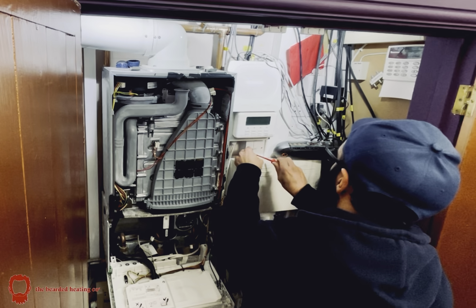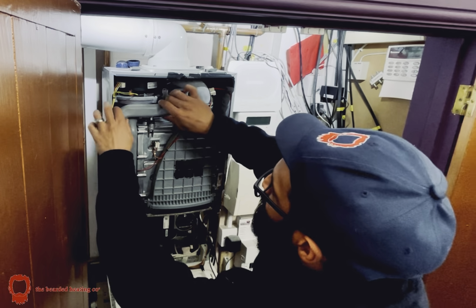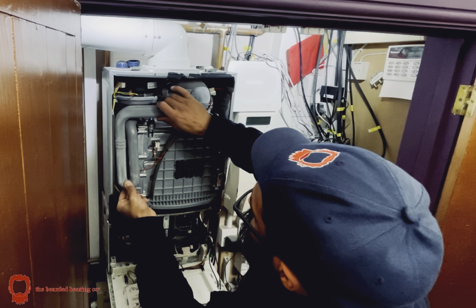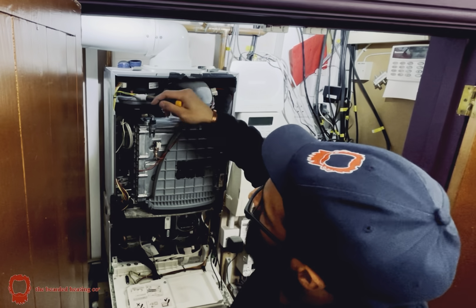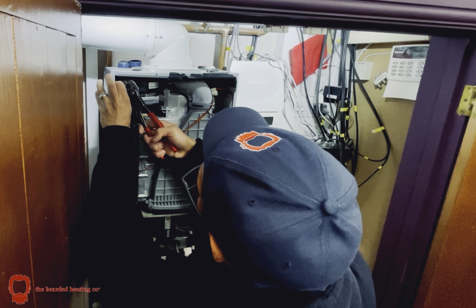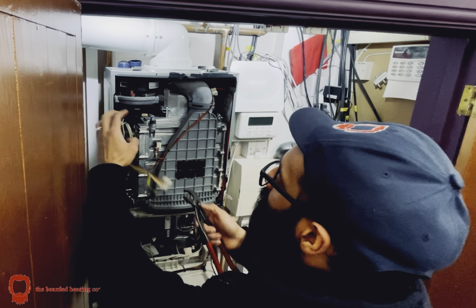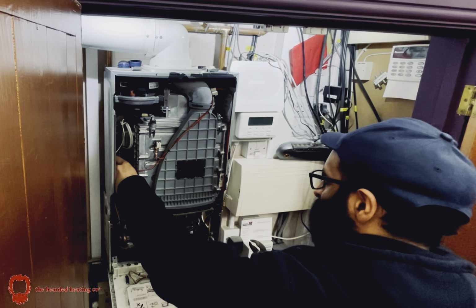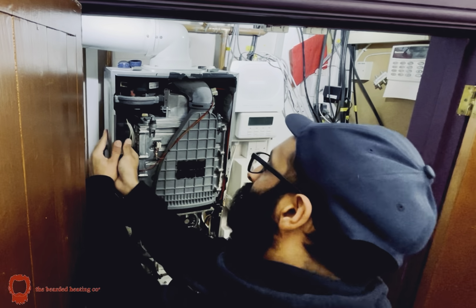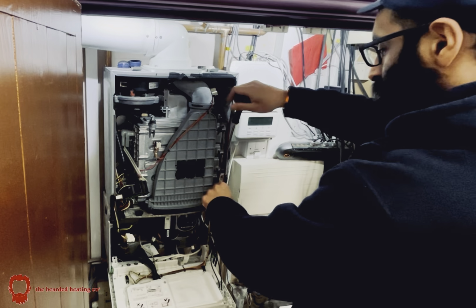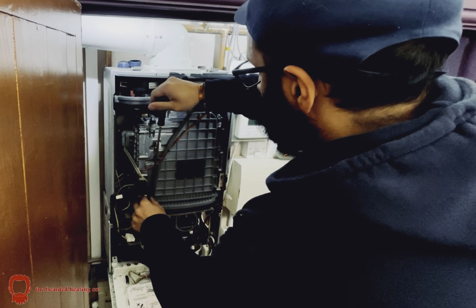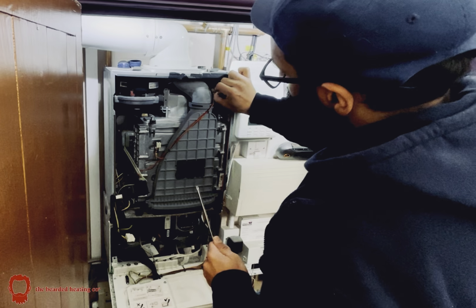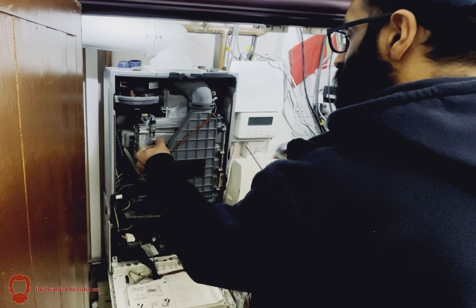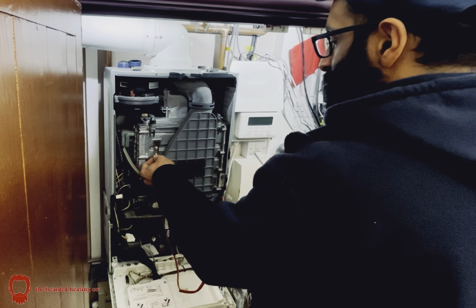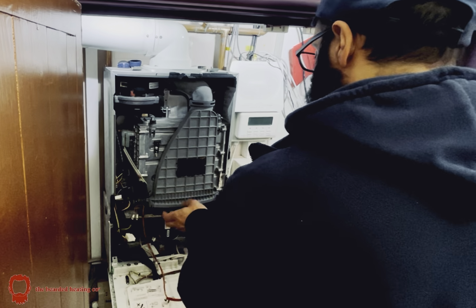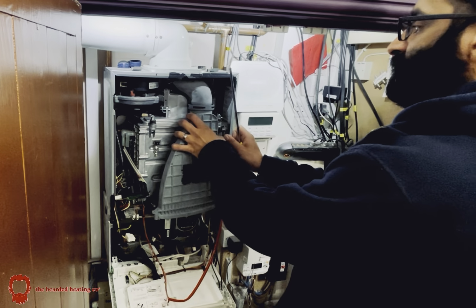I'll just isolate the power again, taking the fuse out. Now to start stripping the boiler apart. First we take out this air intake pipe, and I'm checking to make sure that the power is all dead. Pulled off the fan connector, and now removing the gas pipe and the ignition transformer. Removing the flue collector, taking off the flue stat. That one I believe is the overheat stat. And now that's come out.